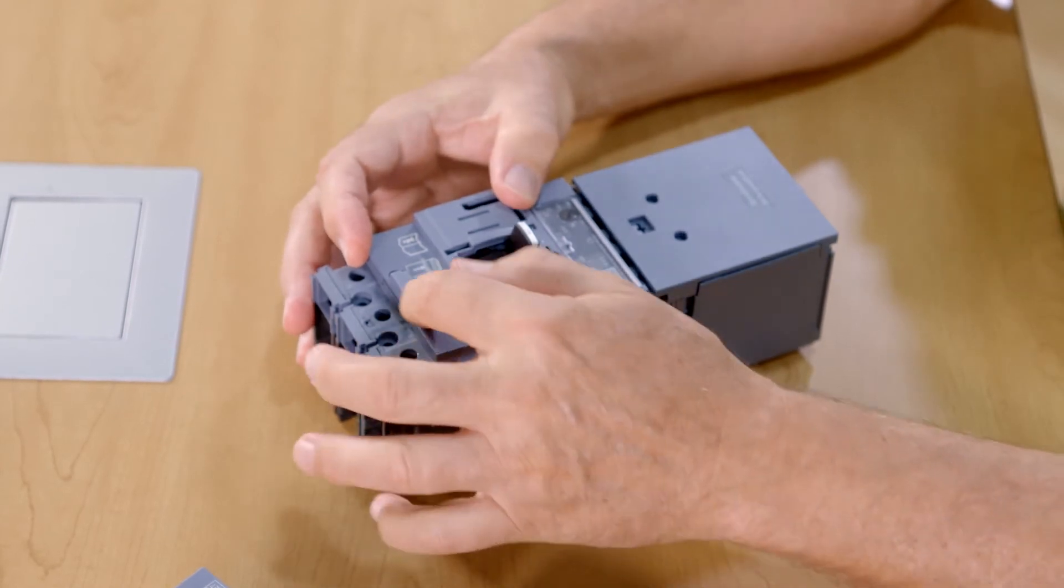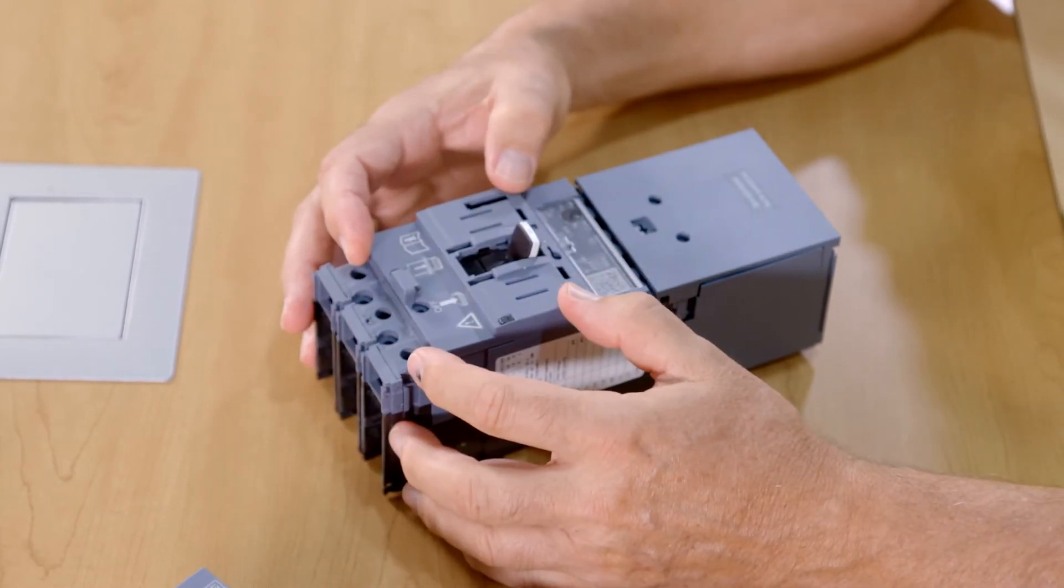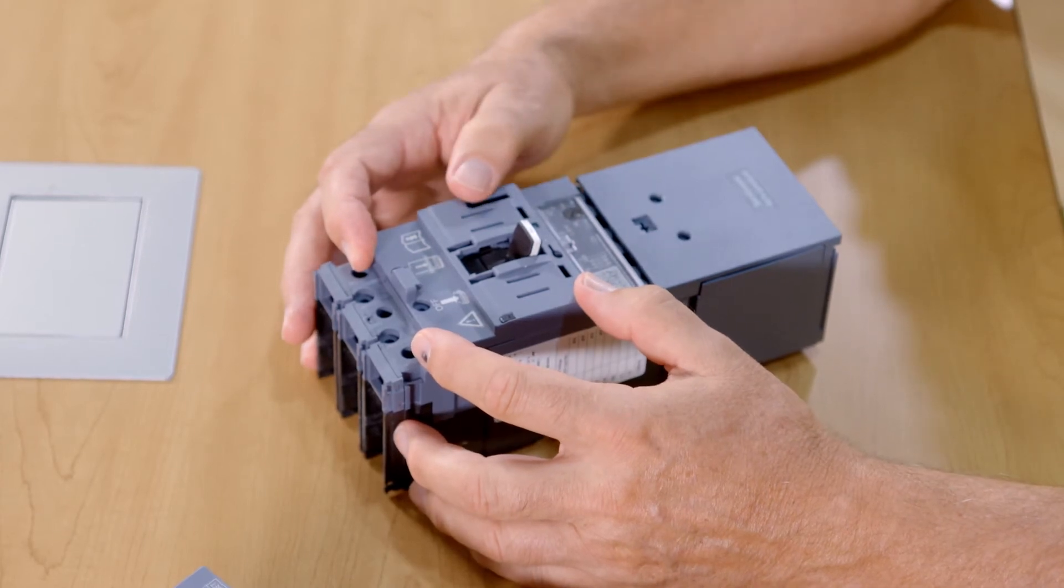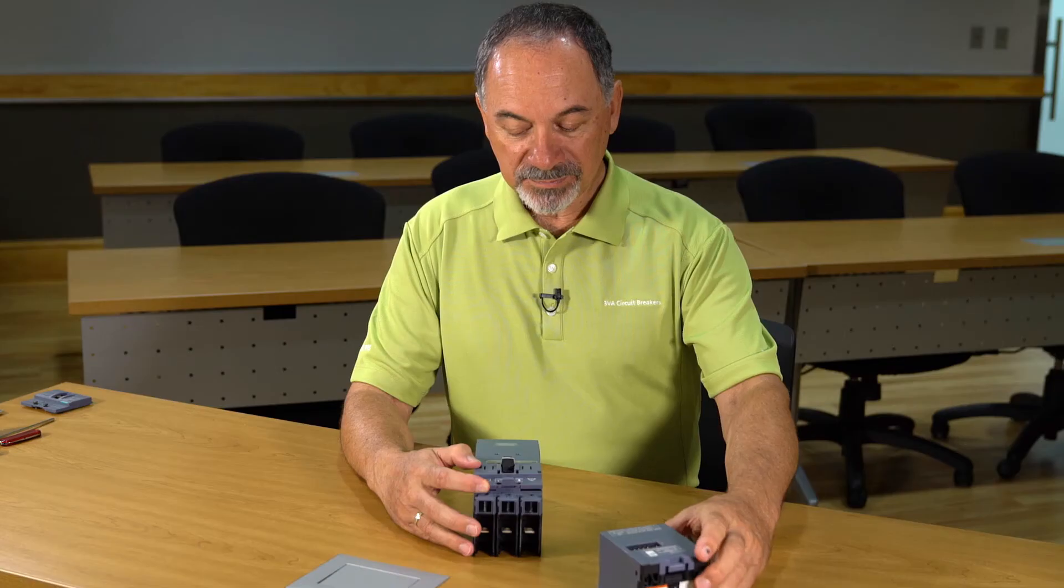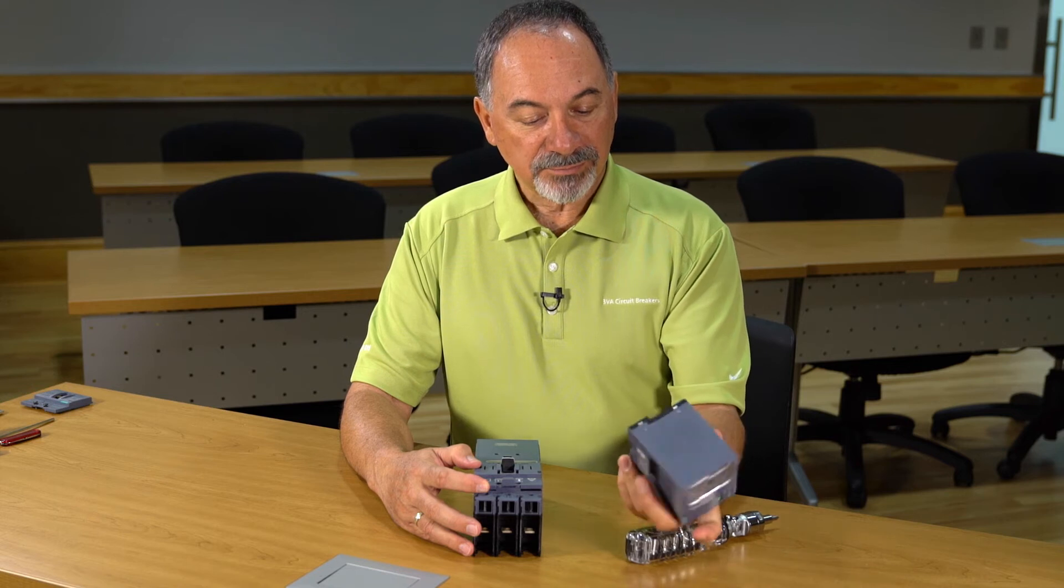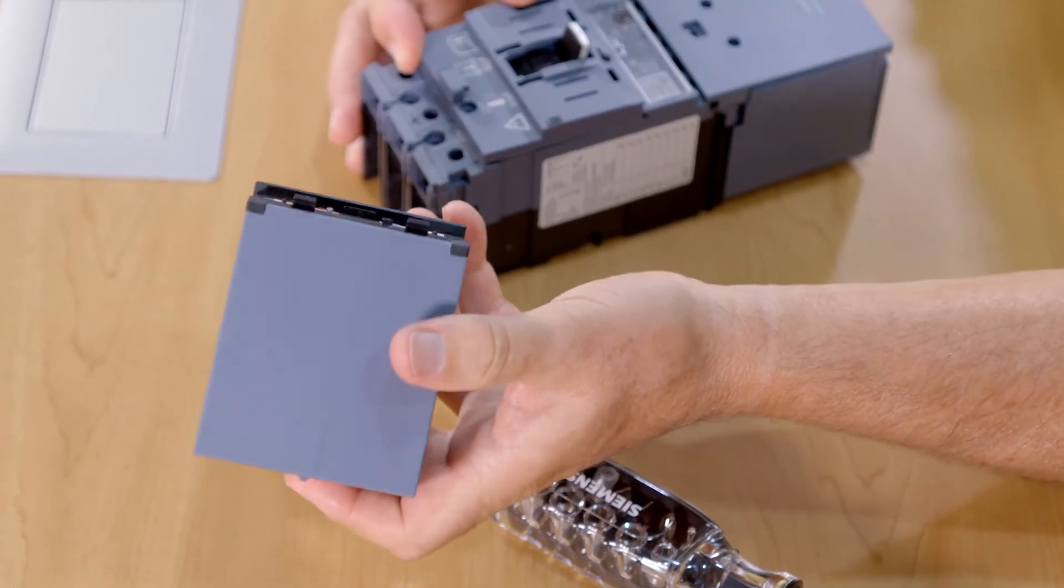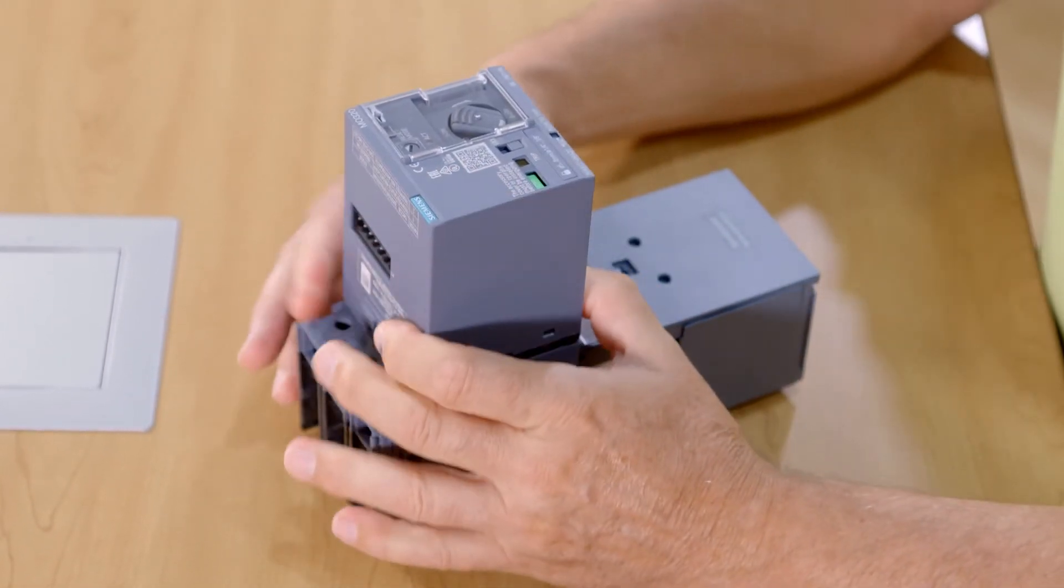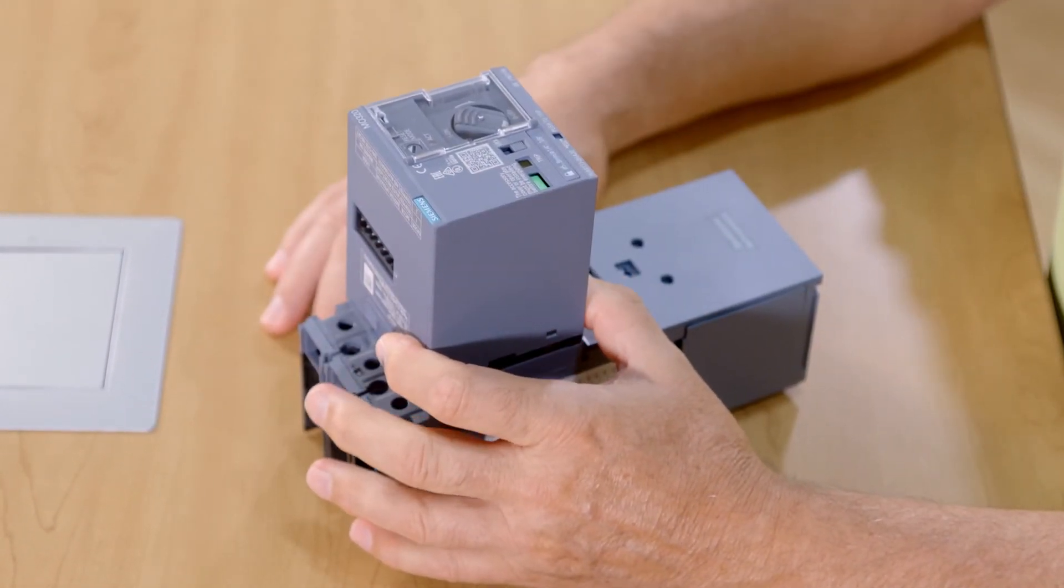Normally, I would use two screws to mount this base to the breaker, but for illustration purposes today, I'm just going to hold it in place. Now, we take the motor operator, there are two hooks on the backside of the motor operator, go into the slots, and it snaps in place. So, your motor operator is mounted.